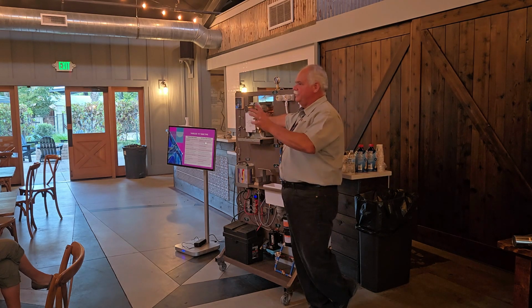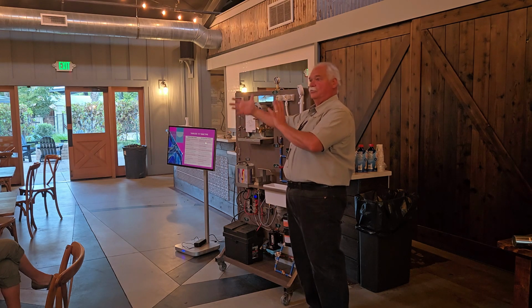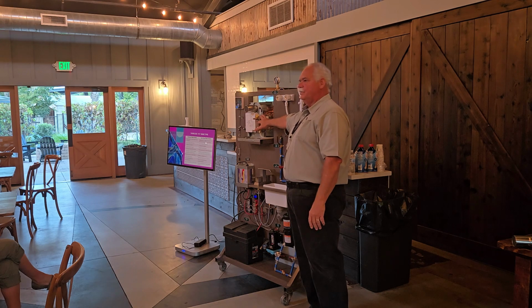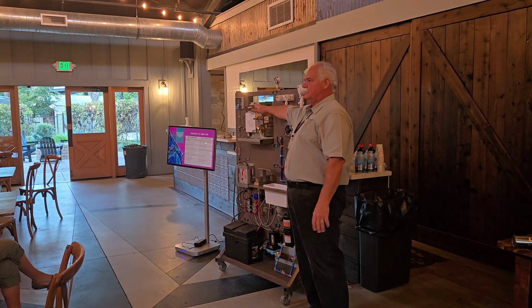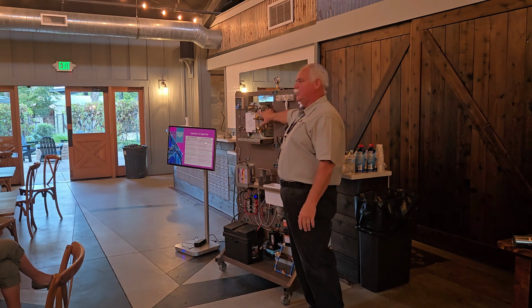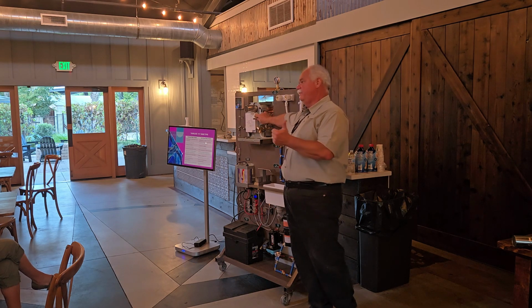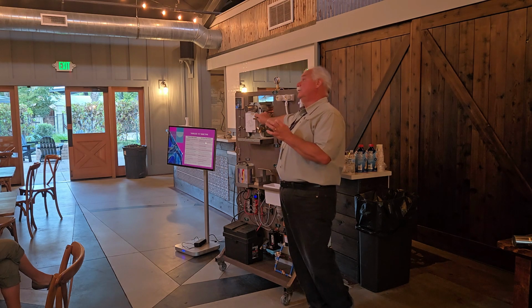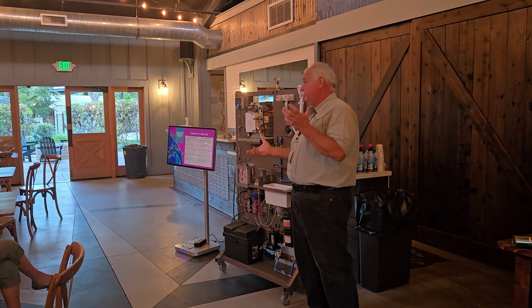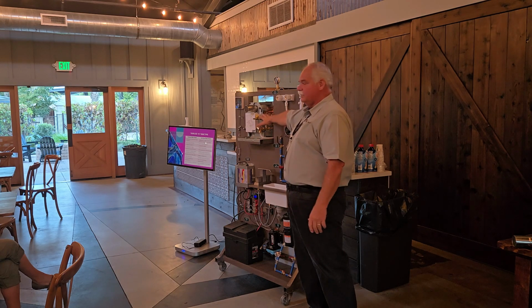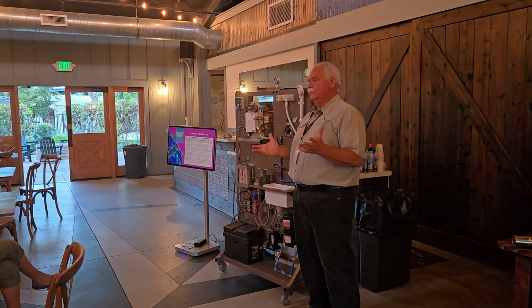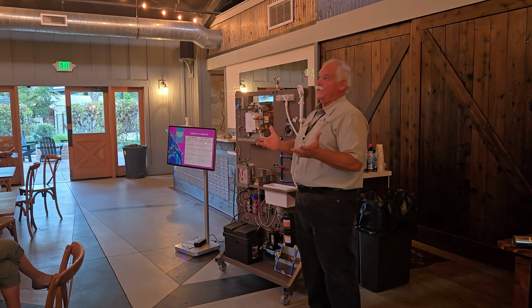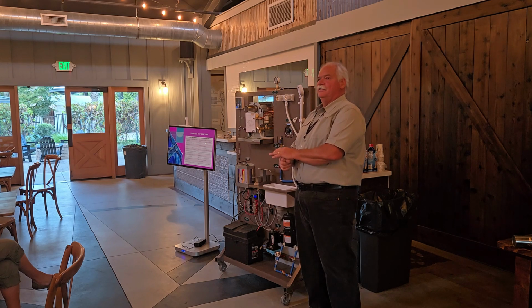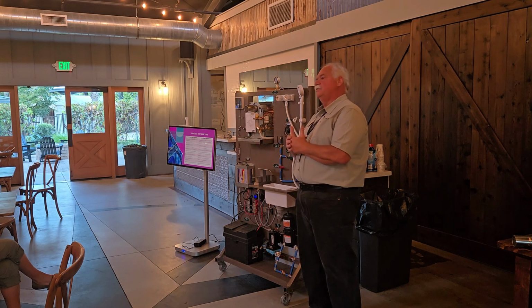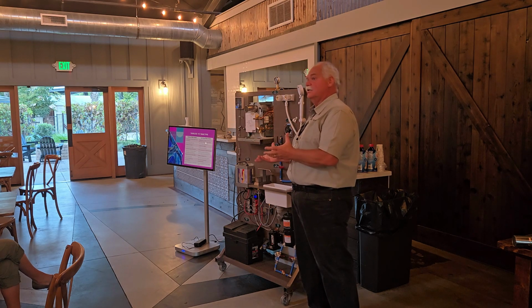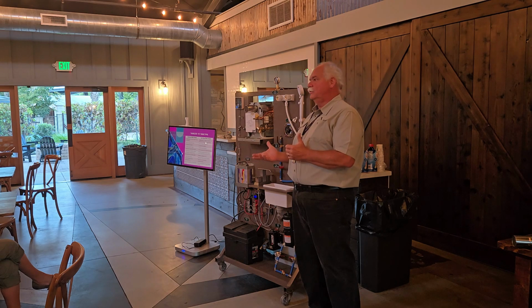You're going to turn on his hot water faucet. Actually, there's going to be some water inside the RV that's probably cool because he's got his air conditioners running. It might fire up, but as soon as that hot water from that hose gets to that sensor, it's going to say, hey, we detected an error. Incoming water temperature is too hot. Shuts off. With 50 feet of 3/4-inch hose, it's going to take a long time, probably 5 gallons of water, until that groundwater, maybe 70 or 80 degrees, is cool enough that the water heater is going to turn on, and then he's going to get hot water. So he's going to see it come on for maybe a few seconds, turn off, and he's going to have really hot water because it's coming out of that dark hose, and then all of a sudden he's going to get cold water.